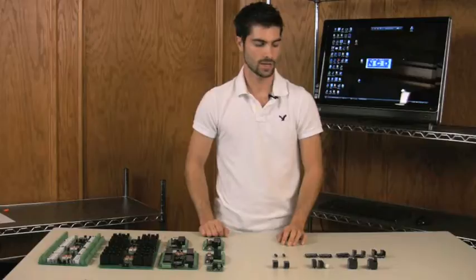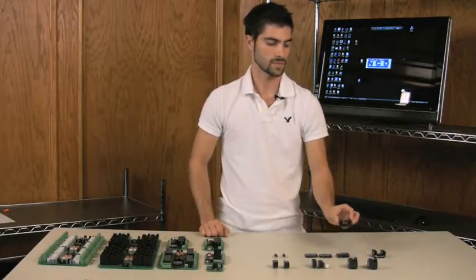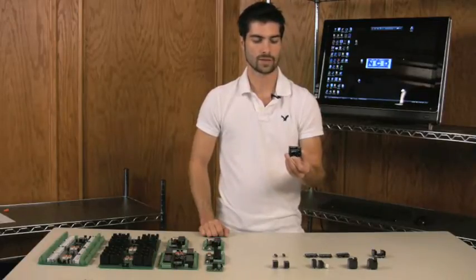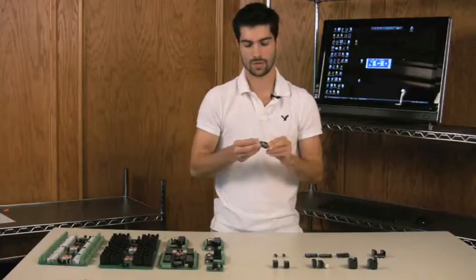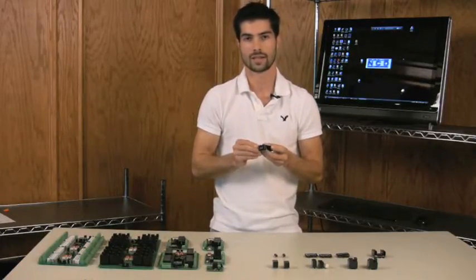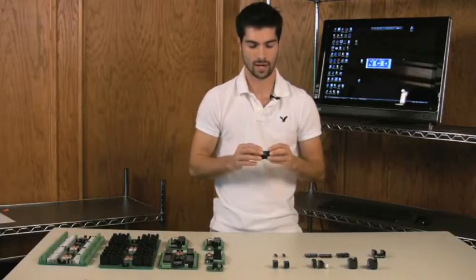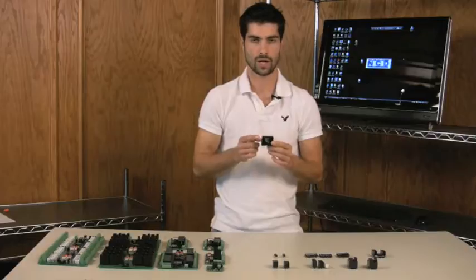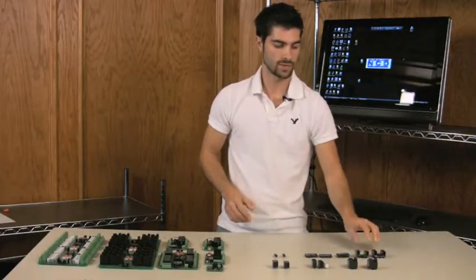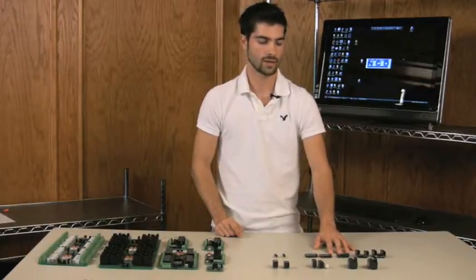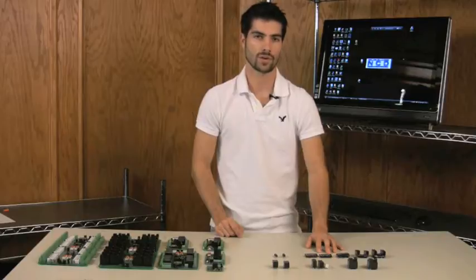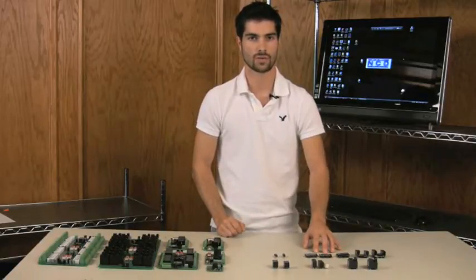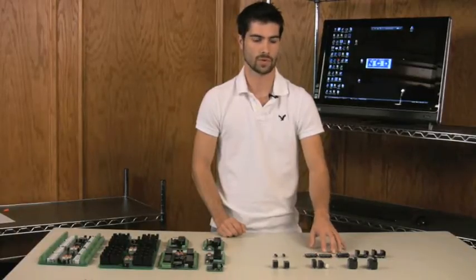When you're switching AC current, sometimes it's not a bad idea to consider solid state relays. These relays make their switch electronically, so there's no mechanical moving parts, which is kind of where the electronic industry is trying to go with solid state hard drives and things of that nature. So these are highly reliable, but only good for switching AC current. We do not offer these to switch DC current. We have a few different types here. We have a couple of them that are capable of switching inductive loads, and the rest of them are capable of only switching resistive loads. If you don't know what an inductive load is, we have a video on our website as well as an article describing what induction is. So be sure and review that video and see what type of load you're switching before you actually select a relay.